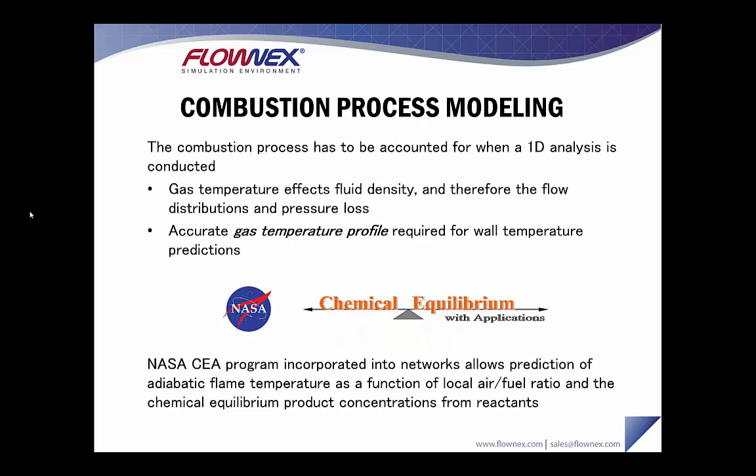The combustion process is also very important to take into account. Gas temperatures affect fluid density and therefore the flow distribution and pressure loss through your network. An accurate gas temperature profile is required to calculate wall temperatures. Within Flownex there is a NASA CEA program that can be incorporated into networks and allows the prediction of an adiabatic flame temperature as a function of local air-fuel ratio, and it will also calculate the chemical equilibrium product concentrations from reactants.